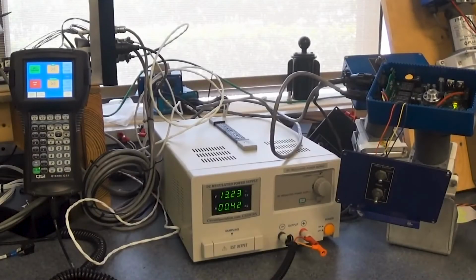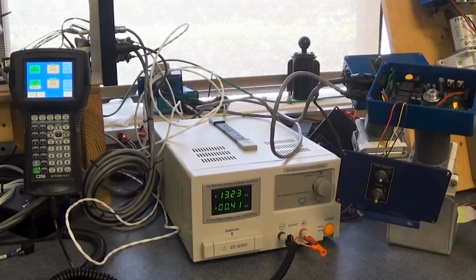Okay, so here we have a monitor attached to a variable flow pump. Now, one thing that may happen from time to time is if we tell it to spray, notice that on our screen here, we have a flow rate of 0.0 ounces. But obviously, you can hear the pump running, and it's running at full bore. This isn't good.